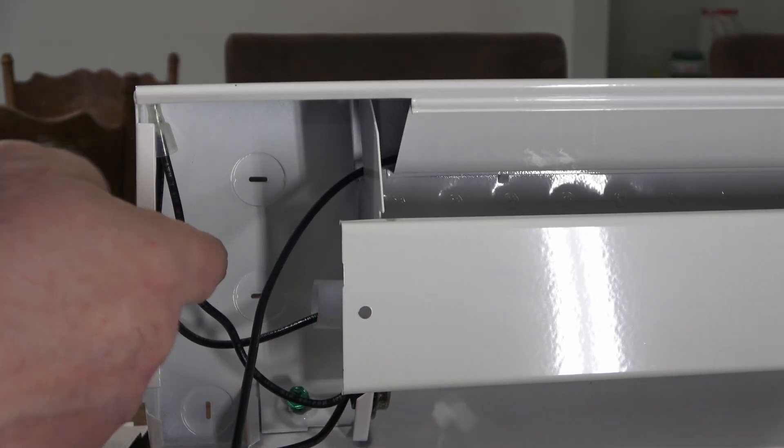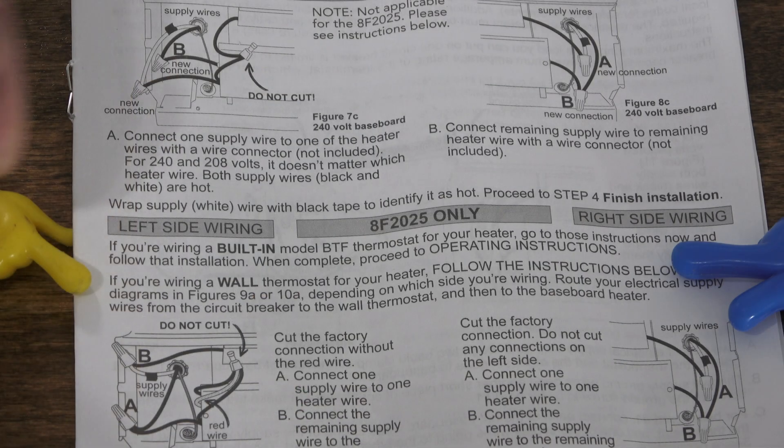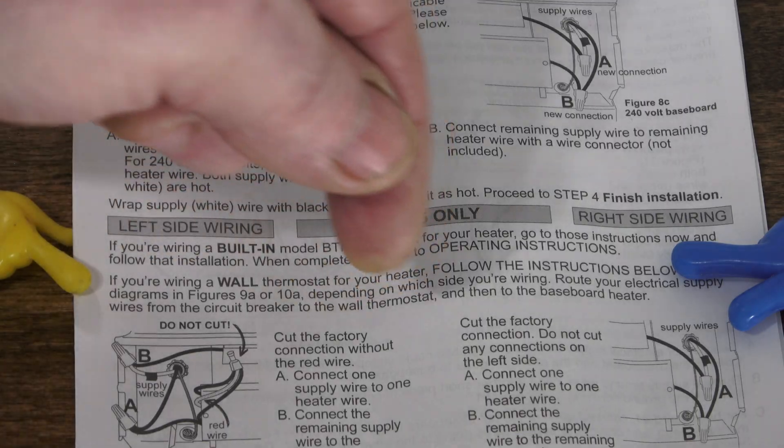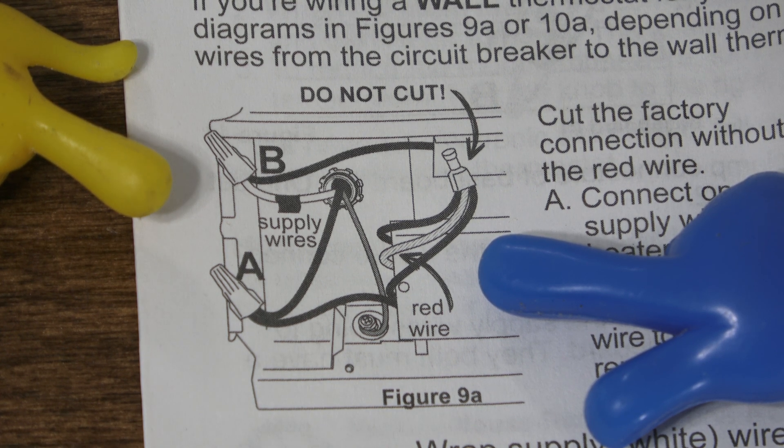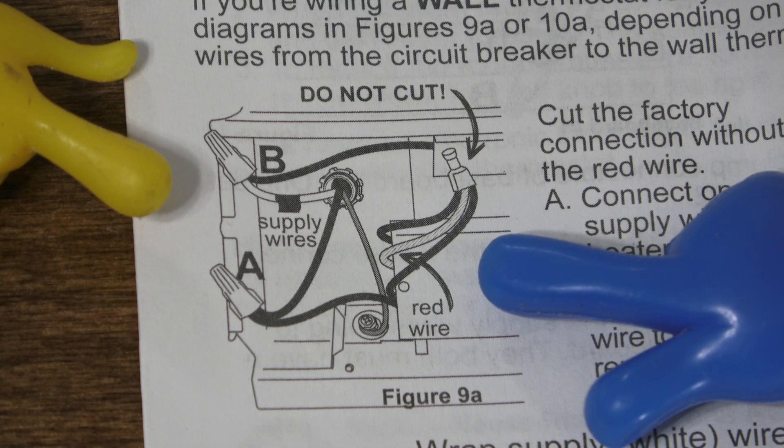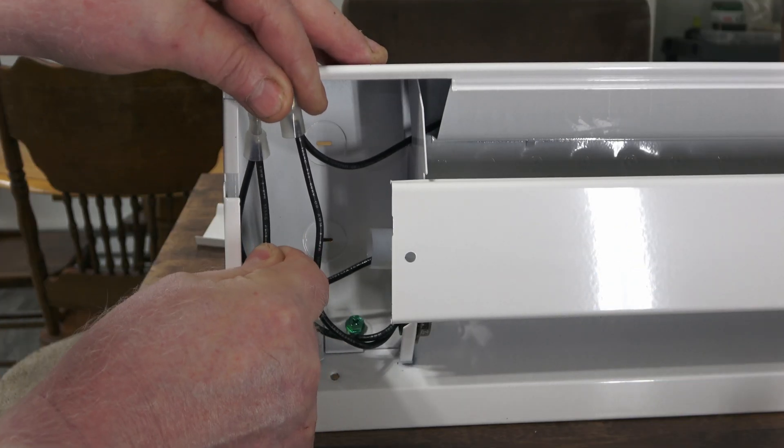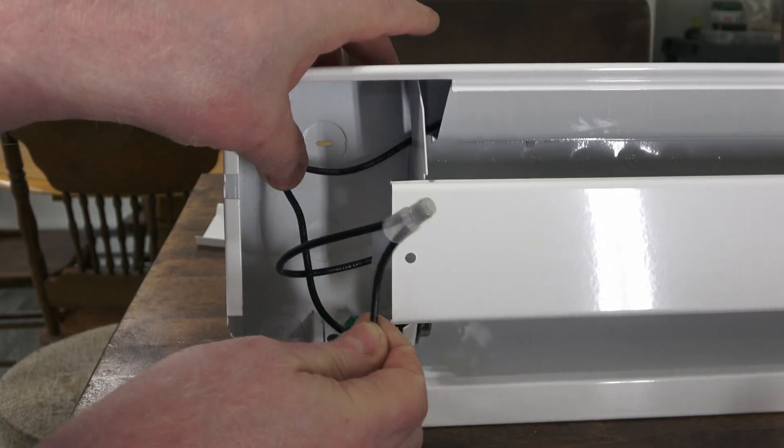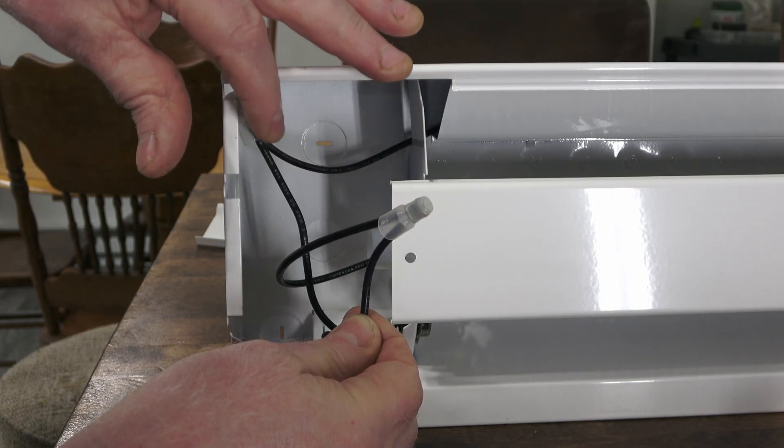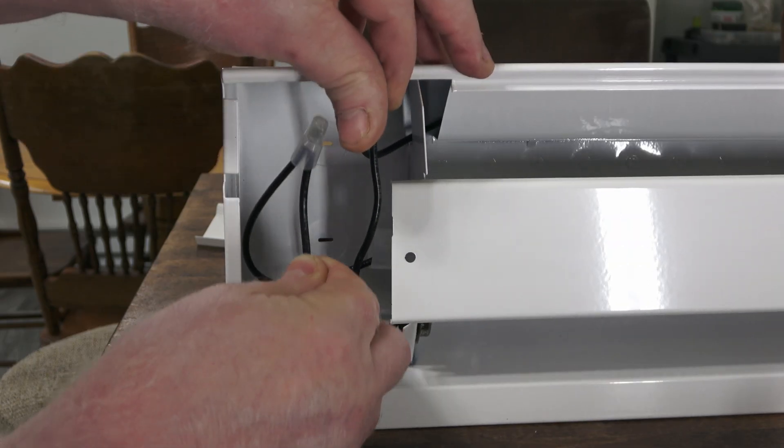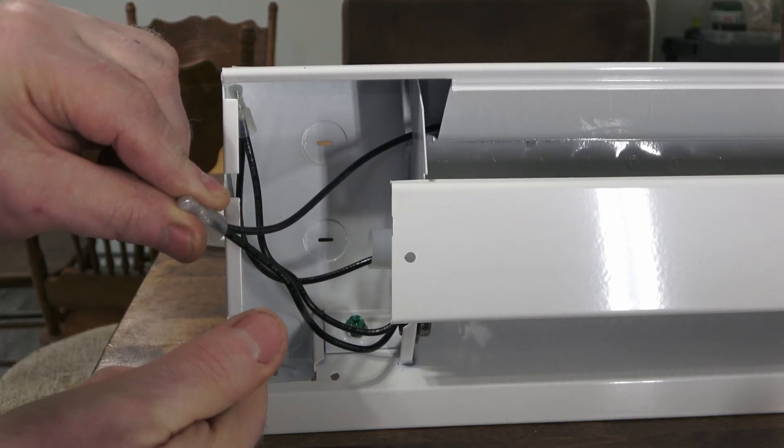This one is the loop that carries power through the heating element. Here it states if you're using a built-in thermostat, you go to that procedure. And this section is the procedure for a wall thermostat, which is what I'm using. The blue pointer represents the factory wire you do not cut. A and B is the power coming from your breaker panel, 120 volts each leg. So I'm going to swap the wires and show that diagram. This is the wire you do not cut. And these two wires get the power from the breaker panel.